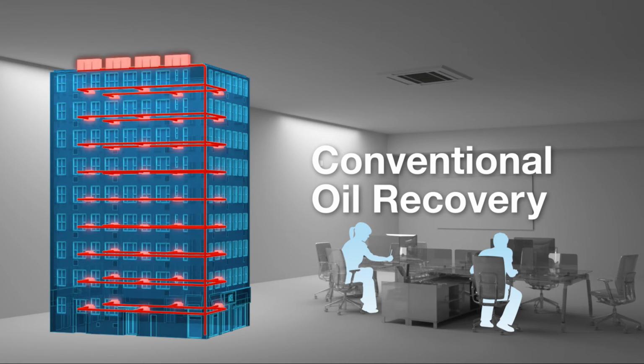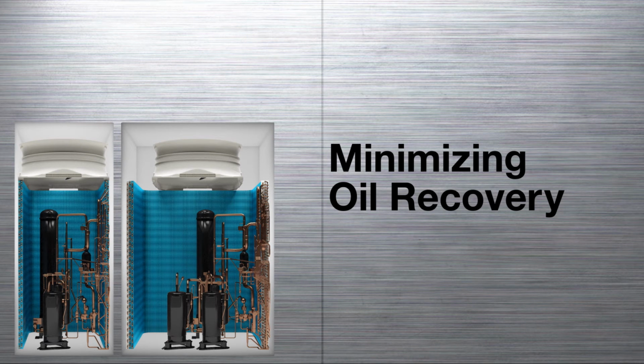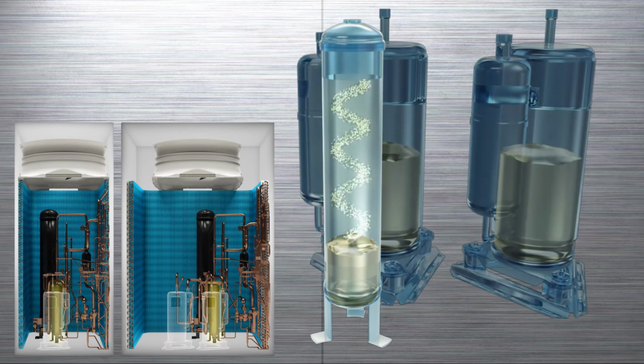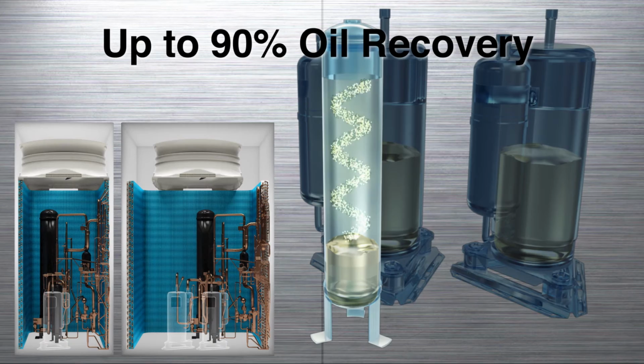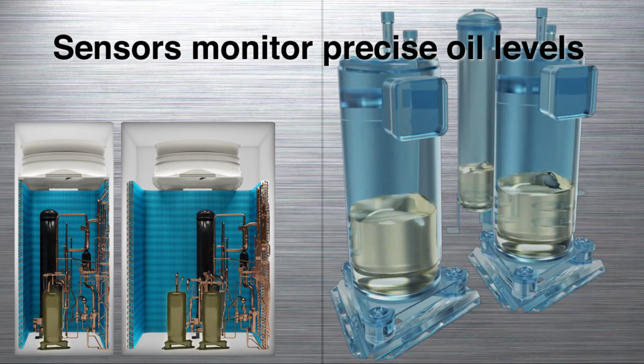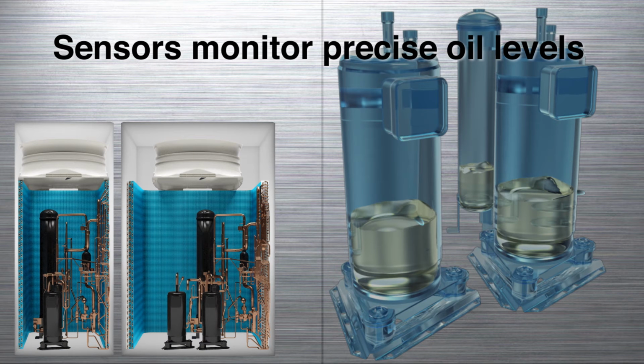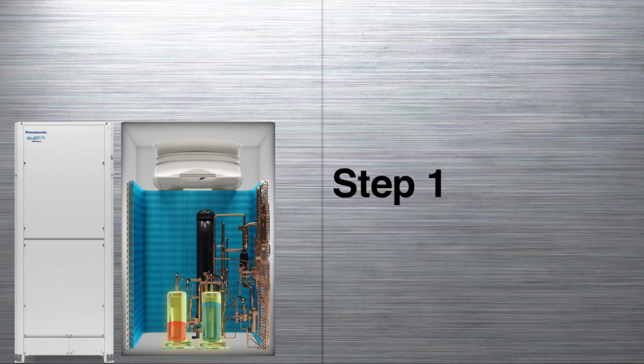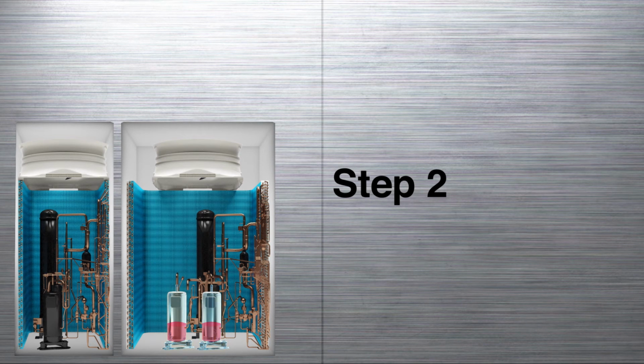However, the Panasonic approach is completely different. It dramatically minimizes the frequency of unnecessary oil recovery. To begin with, ECOi-EX's oil separator recovers up to 90% of oil. Moreover, oil sensors equipped on each compressor precisely monitor oil levels. There's more: a unique two-step oil recovery system, which conventional systems do not have. Step one, when a compressor's oil level falls, oil is transferred from the other compressor within the same outdoor unit. Step two, when oil level is low in every compressor within the outdoor unit, oil can be replenished from adjacent outdoor units. As a result, the ECOi-EX drastically minimizes oil recovery.